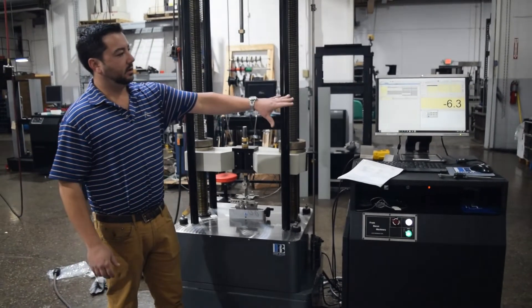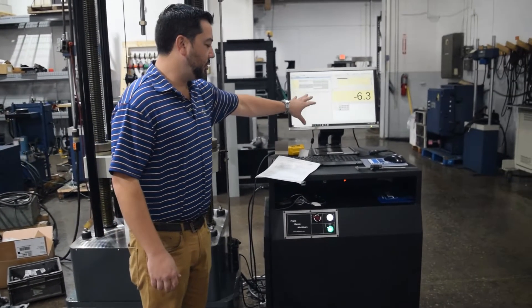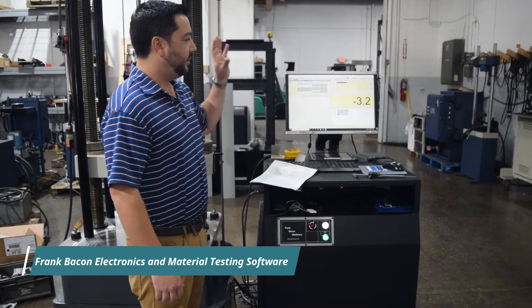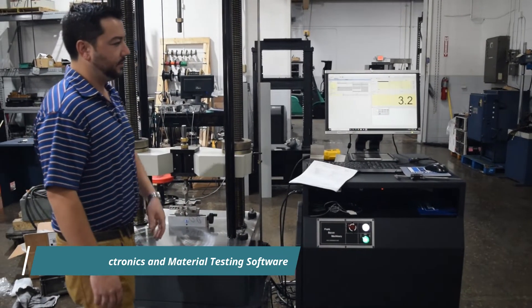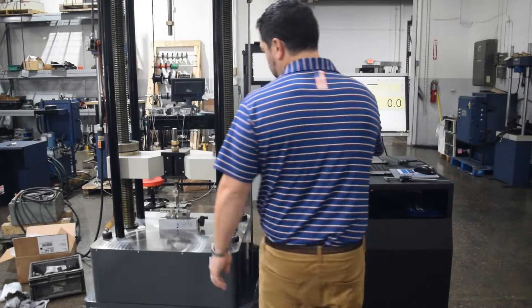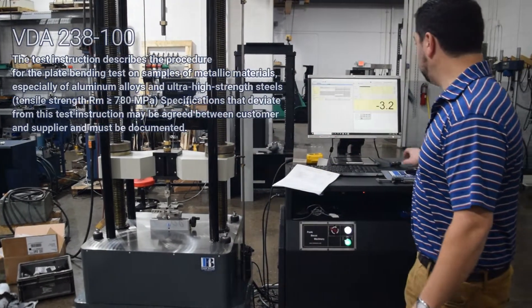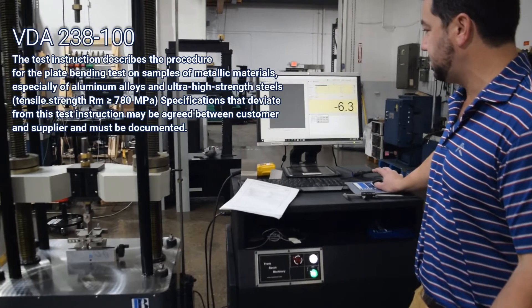We're using our software control here to program per spec the preload and test rate that we need to bend this material. At this point, once we're set and the specimen is in place, all we need to do now is make sure we're zeroed and press start.